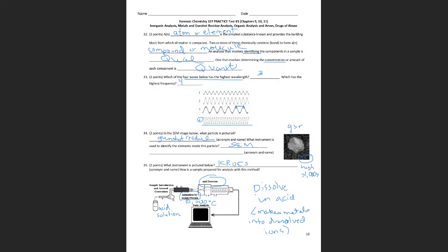We need to calibrate it with solutions of known composition. So you create calibration curves. If you watch the video of the scientist explaining that process, she showed you calibration curves. And the cool thing is it will instantaneously analyze over 20 different elements at one time, because you'll run a mixture of all those elements in your calibration standards. You'll have your cal curves set up in the computer. And once you put your samples in, the computer will very quickly calculate which elements are there and what their concentrations are.